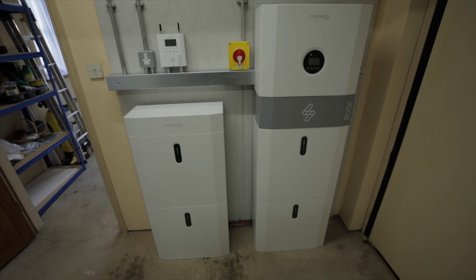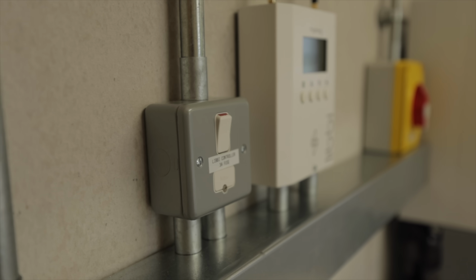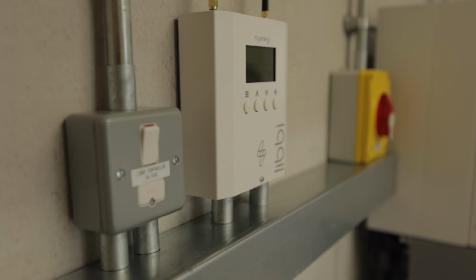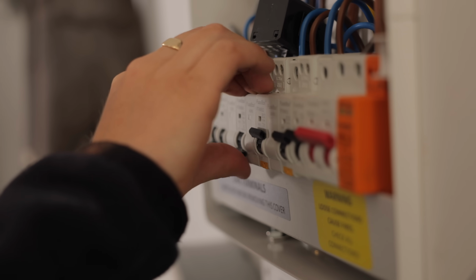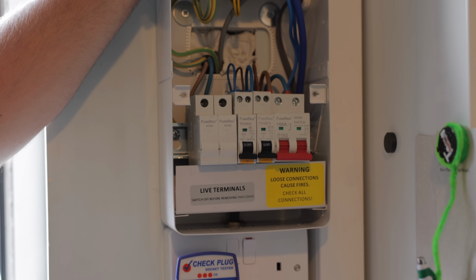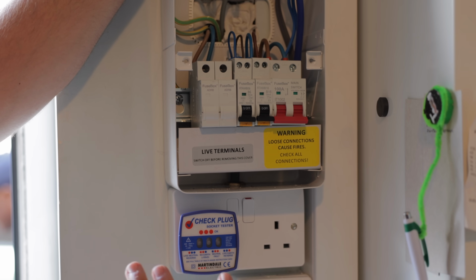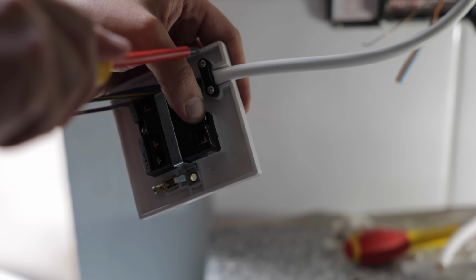Now, the third type of backup system that we come across quite frequently is what we call backup circuits, or emergency circuits. This is where an inverter has a set of terminals designed for backup, but usually the amount of power those backup terminals can supply is quite minimal, maybe 3 kilowatts, 16 amps, something like that. So the idea behind those is that you can wire from the inverter to a separate backup consumer unit and just put your essential circuits running off of that backup consumer unit, or maybe just run a couple of sockets off of those backup terminals.